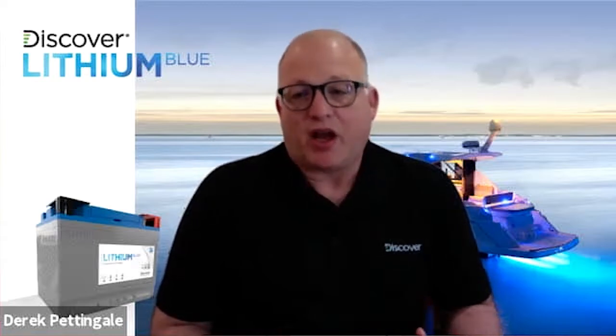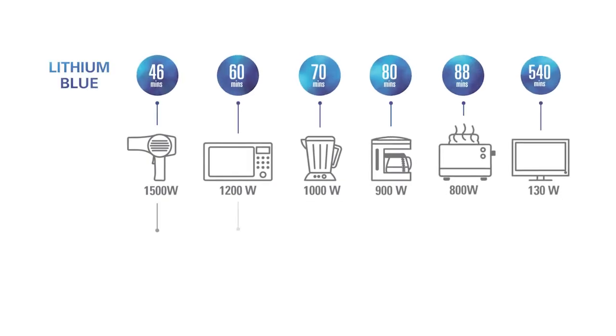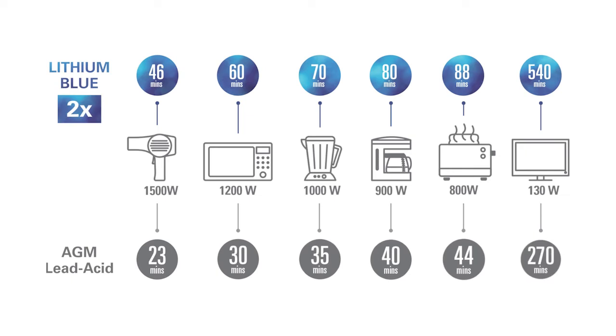They're lighter weight than those lead acid batteries, which is one of the first advantages lithium will have - about half the weight of a comparable lead acid, same volume. So they've got about half that weight, and additionally they store about twice as much energy. So if you have a 100 amp rated lead battery and a 100 amp lithium battery, the lithium has got double the accessible capacity because you can take that full 100 amps to 100% depth of discharge - you're not doing that with lead. It's a 50% recommended max discharge on lead. So a number of differences there in terms of same size, same volume, higher energy density, lower weight.